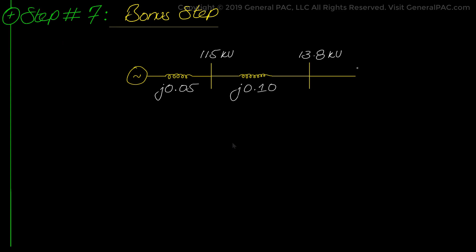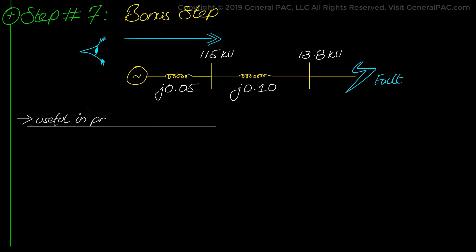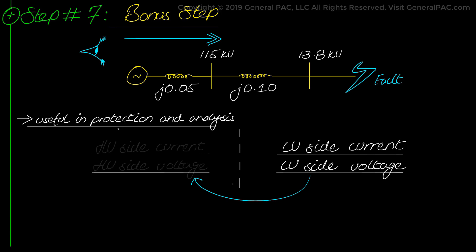Up until now we have been seeing calculations and methodologies on faults on the low voltage side of the 13.8 kV transformer in our example. But let's suppose that the fault is still on the 13.8 kV side of the bus, but we need to know what the same fault current and voltage values are, however this time seen through the high voltage side of the transformer or the 115 kV side of the bus. This is useful for many instances in power system protection and analysis, so we will reflect the fault current and voltage quantities from the low voltage side towards the high voltage side.